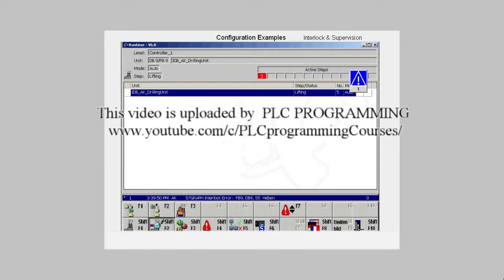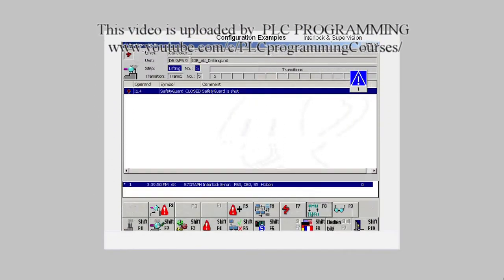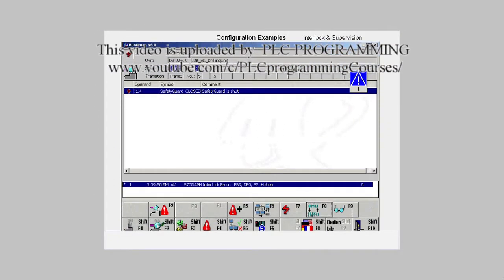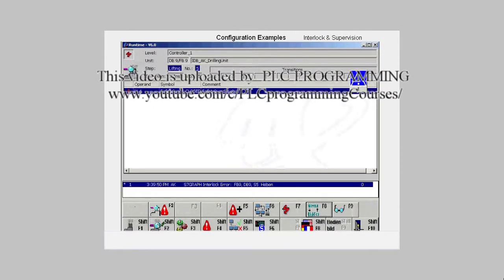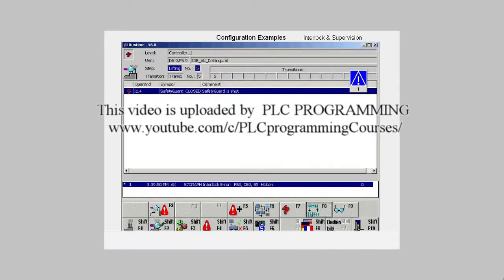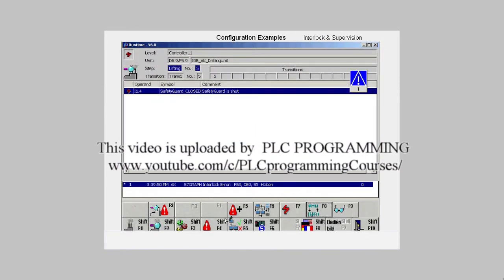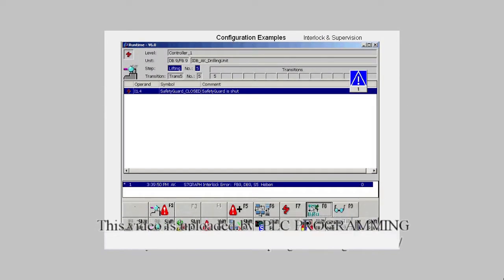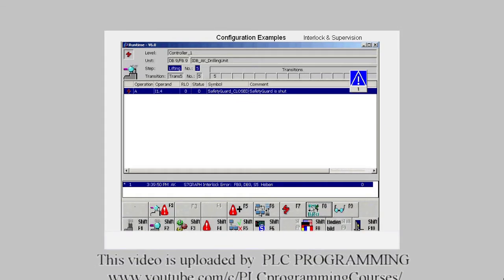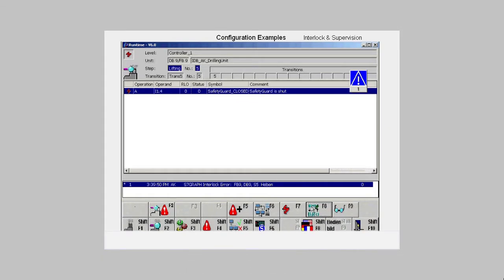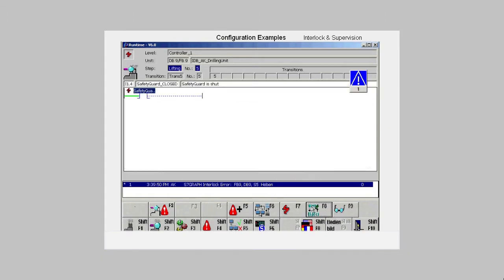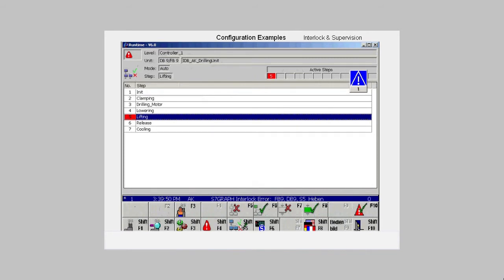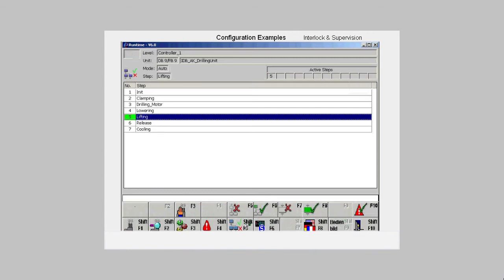In the detailed picture, we see the step concerned and the transition as well as the address that caused the fault. With the F8 button, we switch to the statement list and ladder views to see how the address is linked in the program. In the sequencer view, just as with the supervision fault, the number of the faulty step is marked in red.